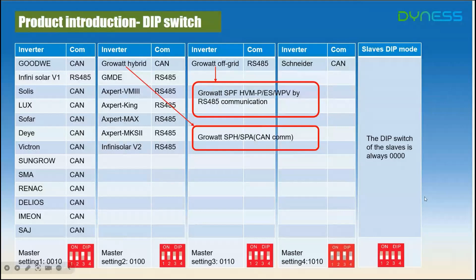And now let's see more about the communication cable, because I have seen many problems during installation, and people may use the wrong communication cable. First, we need to know the different communication cables. This picture shows a standard network cable with 8 pins. The 8 pin colors are orange white, orange, green white, blue, blue white, green, brown white, and brown. This is a normal standard network cable, and it is used for the battery to battery parallel communication. That means from the master to the slave battery, you need to use this cable with 8 pins. If you use a cable with only 2 pins, the master battery will not communicate with the slave batteries.